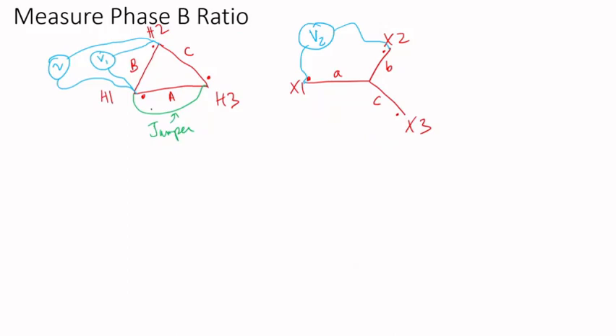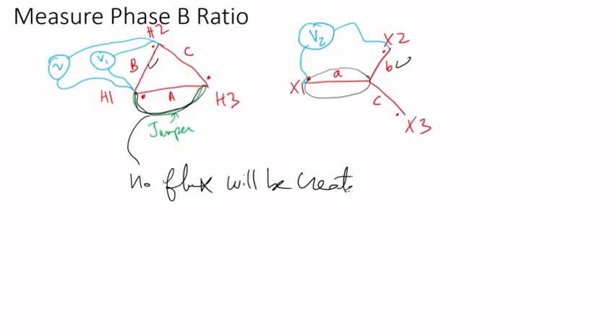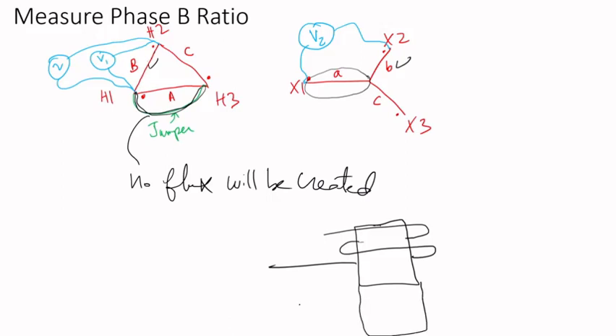I can do the same thing to measure phase B. If you look, phase B is here and phase B is here, but the problem is I need to get rid of this phase. That means I have to short phase A on the delta side, so no flux will be created because it's shorted. Think about it: if this is the core leg, you have the high voltage winding, then, sorry, I'm going to extend this, you have the low voltage winding. Because I shorted this phase, that means no flux. Flux will be 0, so this acts like it's shorted. Now phase A is shorted.